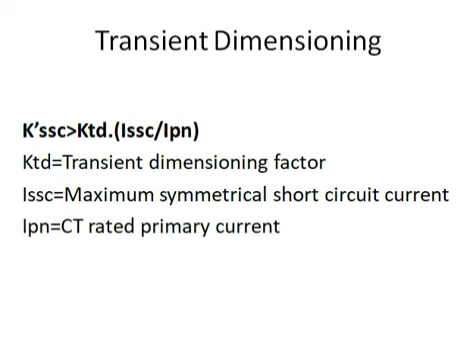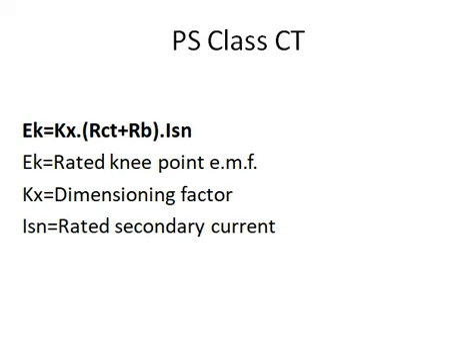This criteria is for a protection class CT such as 5P10 or 5P20. Another protection class is the PS class CT. PS class CTs are generally used for special types of protection, such as differential protection — whether it is bus differential protection, or motor, generator, or transformer differential protection. In those cases we use PS class CTs. We have already discussed the knee point voltage.